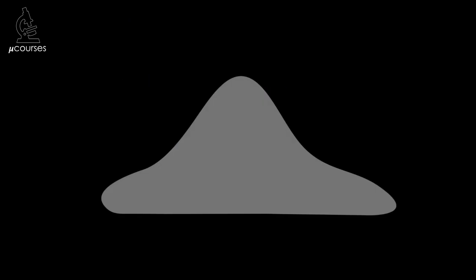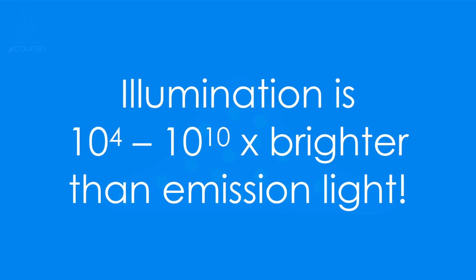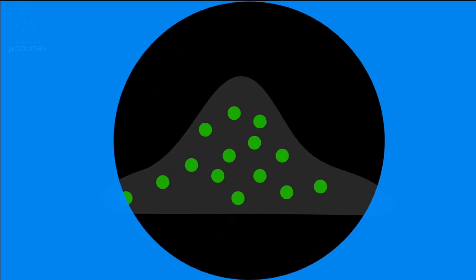Let's say we want to image a cell to which we've added a fluorophore. We illuminate the sample with the wavelengths of light that excite the fluorophore. The intensity of the illumination light is much higher than the intensity of the emitted light from the fluorophore, so the excitation light would completely drown out the relatively small amounts of emission light. We need a filter that blocks the excitation light while allowing the emission light to pass through. This filter is referred to as the emission filter, also known as a barrier filter.